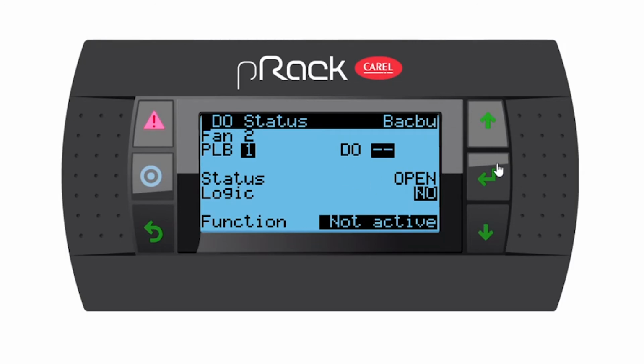If we go down to fan number 2, I'm going to assign it to number 6. It's going to be normally open. If we go down to number 3, I'm going to make that 9. So as you can see, it skipped those SSRs that are already assigned, and it gives me number 9 as the following open digital output. So I'm going to put it on 9, which is a normal relay, and the logic is normally open. And then number 4, I'm going to make it 10. Perfect. Normally open logic, enter and down.